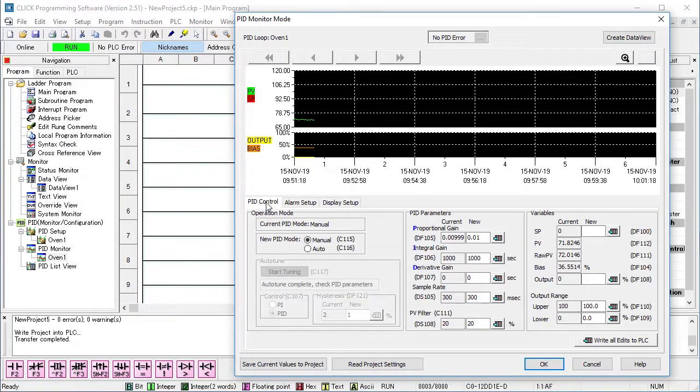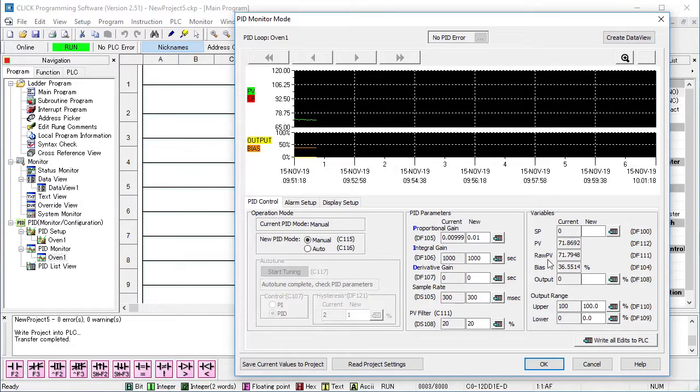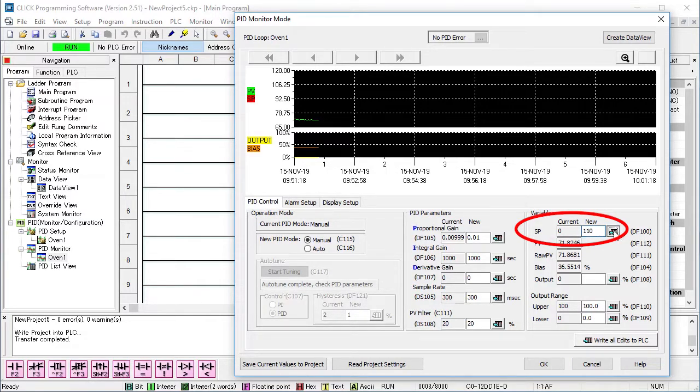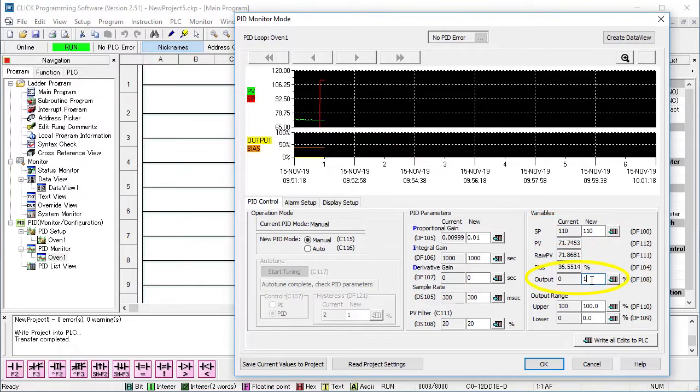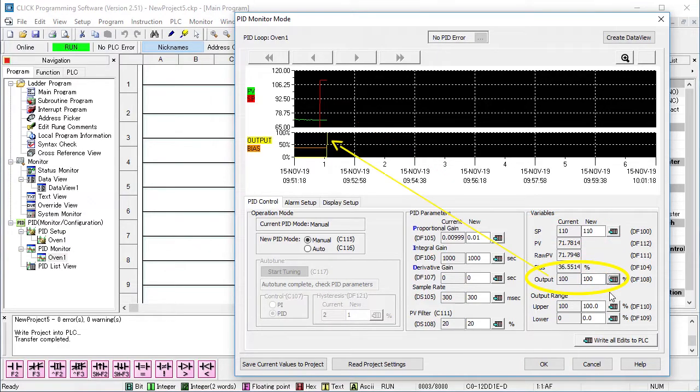To do an auto-tune, start in manual mode and put the set point where you intend to operate. Manually adjust the output to get your process within a few percent of the set point.